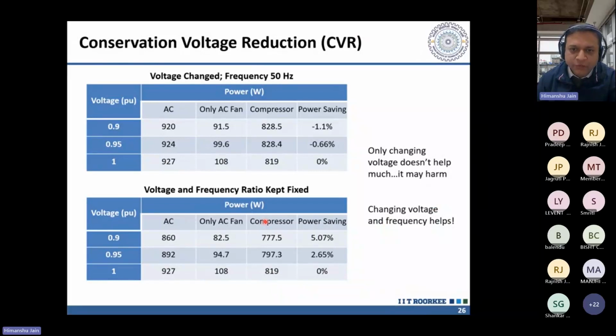When we did a few more experiments, we found that if the voltage-to-frequency ratio was kept fixed, then at different voltage levels, like 0.9 or 0.95, we saw about a 5% difference in energy consumption just by controlling voltage and frequency together.